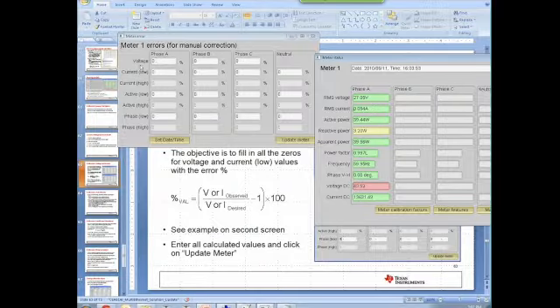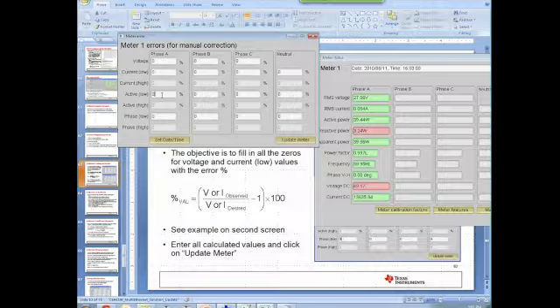So the voltage calibration percent, current calibration, and next we're going to move to active current, or active power. This is the factor your customer is going to care about the most, your active power accuracy. This is the one we output via pulses, so we can get super high resolution measurements out of it. Again, we're just going to calculate it here to show how this scaling works.